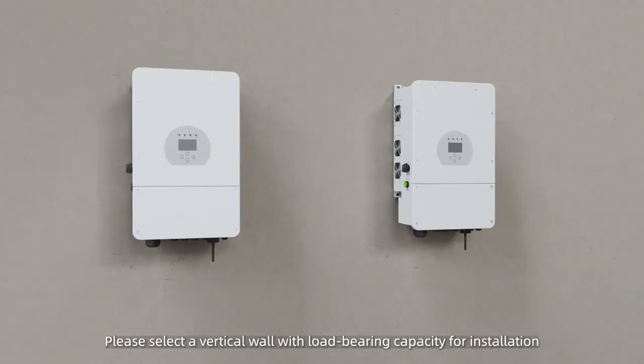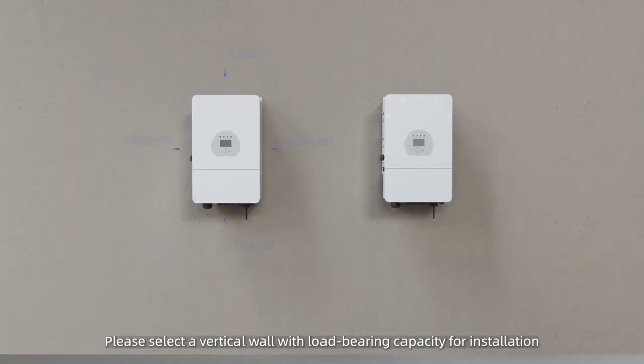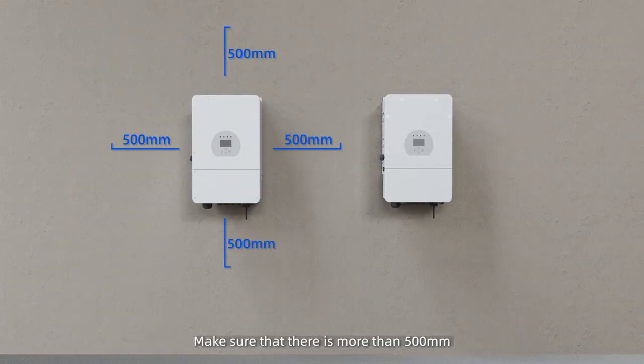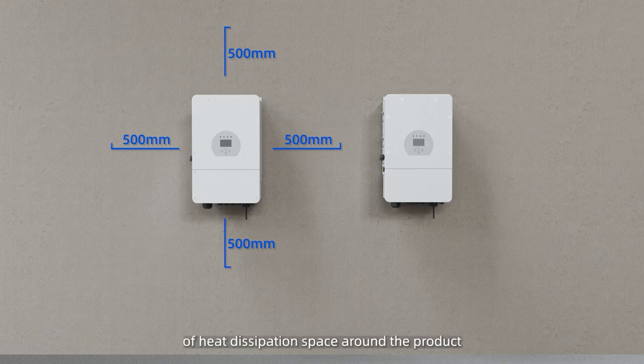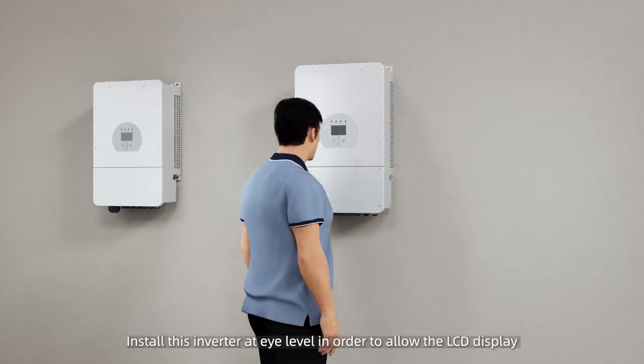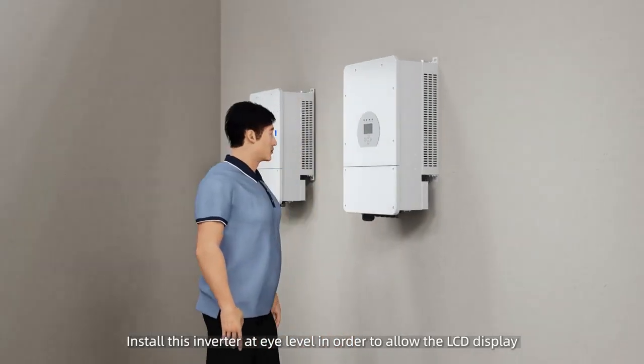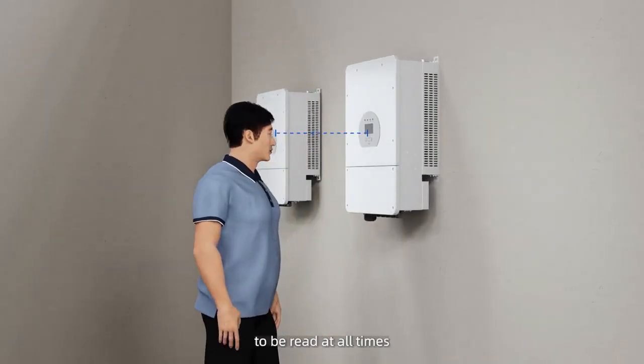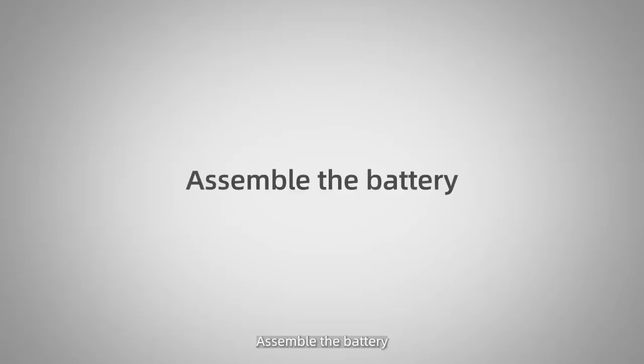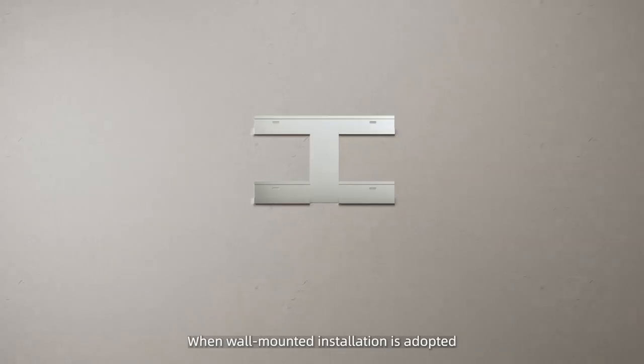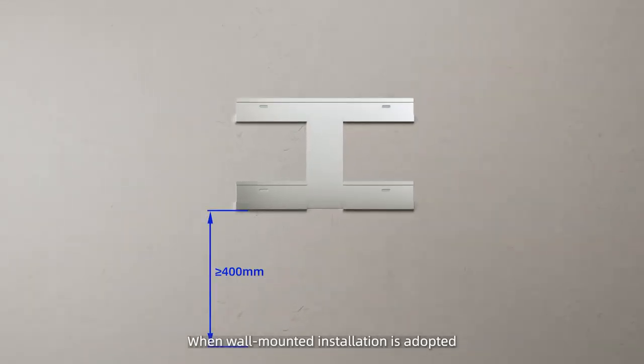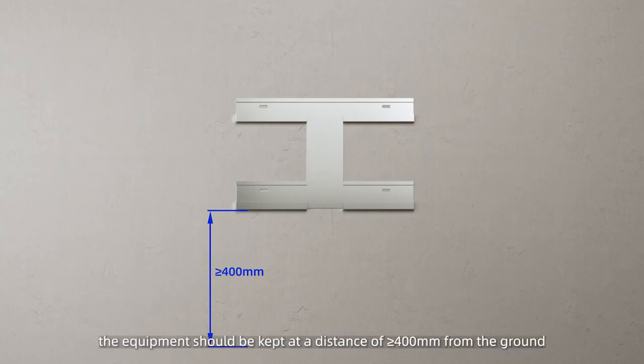Please select a vertical wall with load-bearing capacity for installation. Make sure that there is more than 500 millimeters of heat dissipation space around the product. Install this inverter at eye level in order to allow the LCD display to be read at all times. Assemble the battery. When wall-mounted installation is adopted, the equipment should be kept at a distance of greater than or equal to 400 millimeters from the ground.